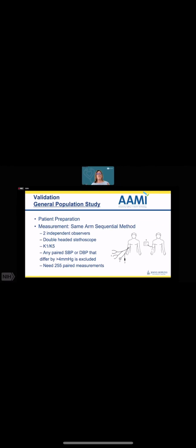They simultaneously determine what the K1 and the K5 is, which is associated with the systolic and diastolic blood pressure. And then once they get their reference measurements, the cuff is removed, and then the device, along with the device cuff, is put on that same arm, and they get measurements with the device under test. Any one of the paired systolic diastolic blood pressures that differ by more than 4 millimeters of mercury is excluded. And you need ultimately, at the end of the day, at least 255 paired measurements.